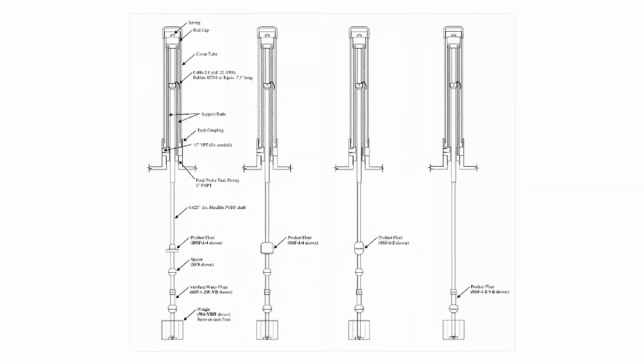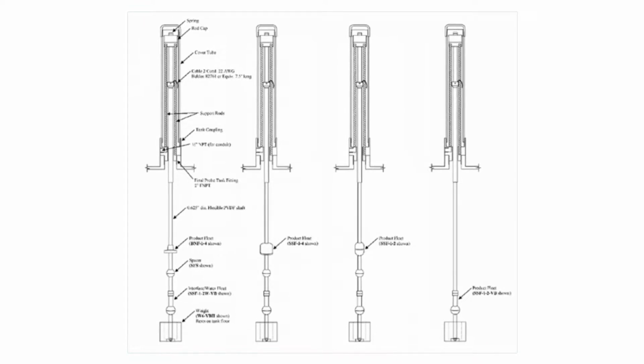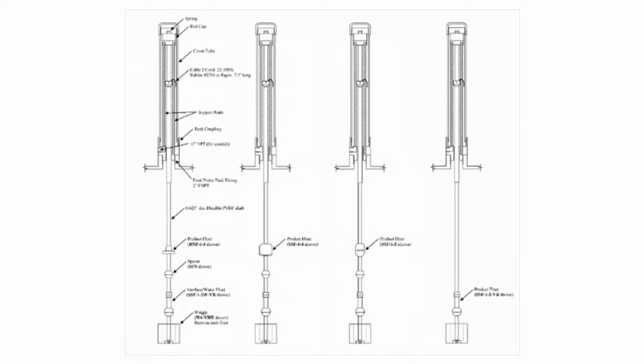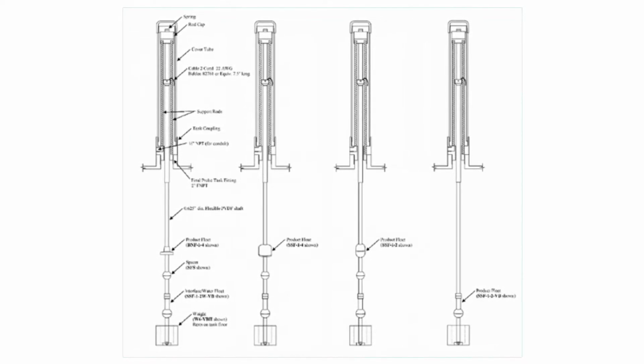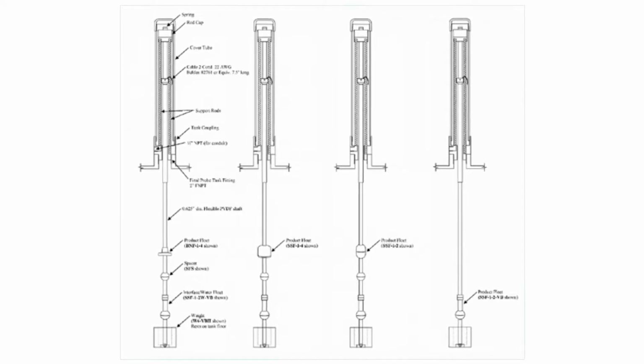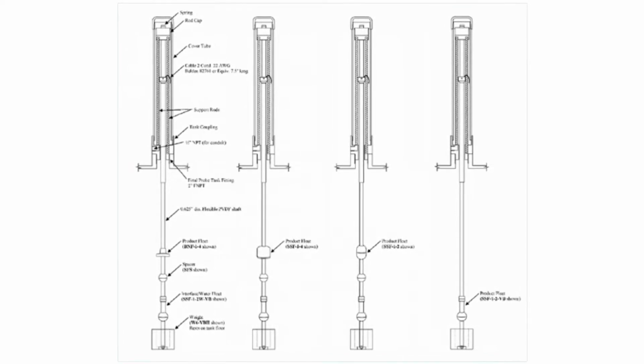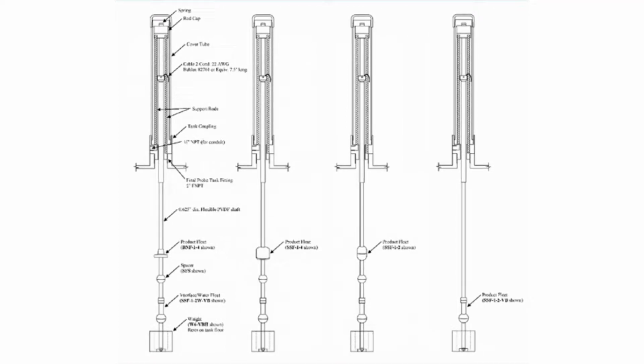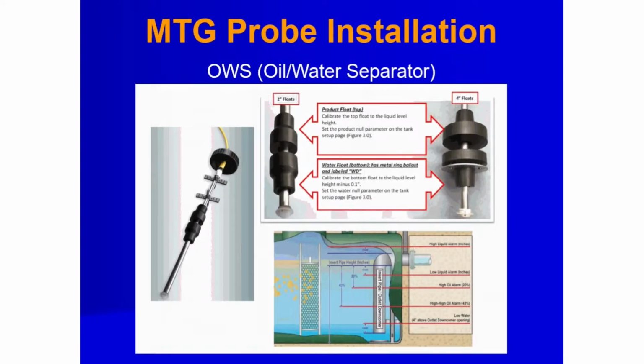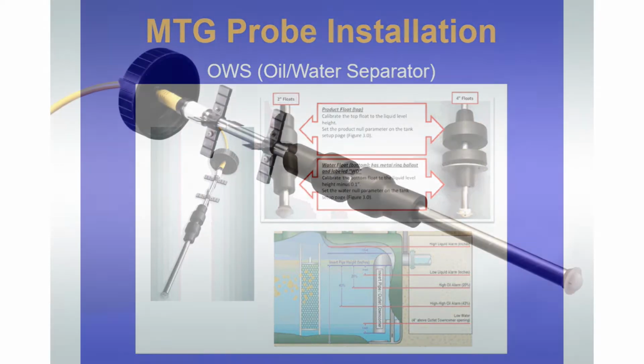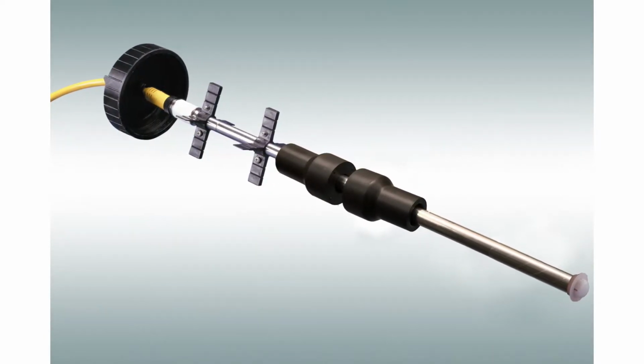A 6-inch opening is required for lowering the probe with the attached bottom weight. A spring assembly is installed to compensate for a floating roof movement. The fixed bottom probe can measure as little as 1 inch of water. The OWS, oil water separator, is a new enhancement to the Proteus features. It utilizes a rigid stainless steel probe.